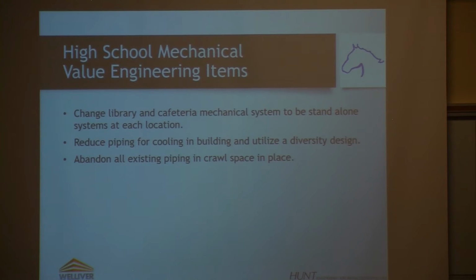But there's a way to reduce the size of piping if we're willing to say, okay, if I'm air conditioning the gymnasium, that probably means all the students are in that gymnasium, so I don't necessarily need to deliver as much cooling to the classrooms at the same time. So you create a diversity model where you're not cooling 100% of the building 100% of the time, but instead managing it so you're cooling the spaces people are actually occupying, since it's unlikely students would be in classrooms and in a full assembly in the gymnasium simultaneously.